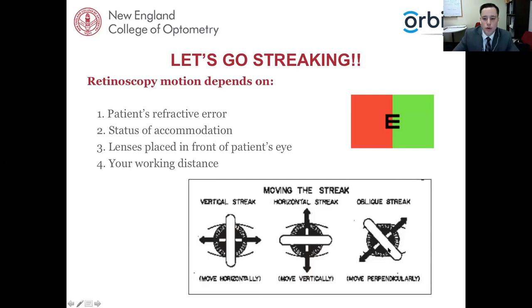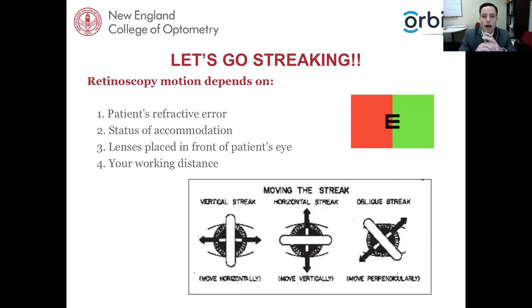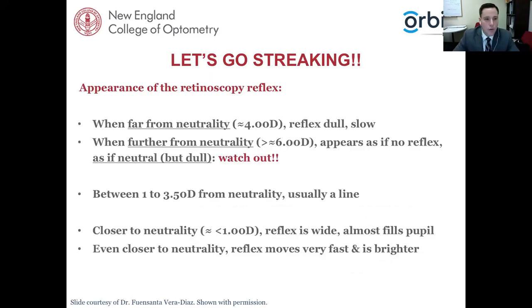Here we have the moving of the streak vertically, horizontally, and obliquely. You need to be comfortable rotating your streak. Spot versus streak retinoscopes come in here — I've only ever used a streak retinoscope. The streak is considered a little bit easier in terms of determining refractive error, specifically as it relates to astigmatism and getting the axis down correctly. Most people use streak retinoscopy today. When you're far from neutrality — about four diopters — the reflex is dull and slow. When even further, greater than six diopters, it almost appears as if there's no reflex.